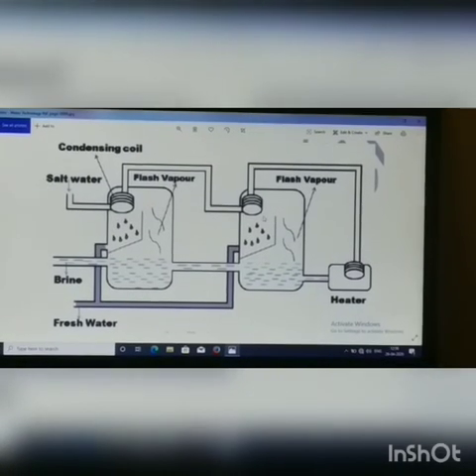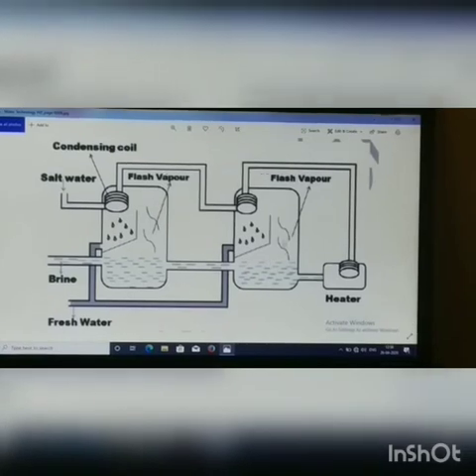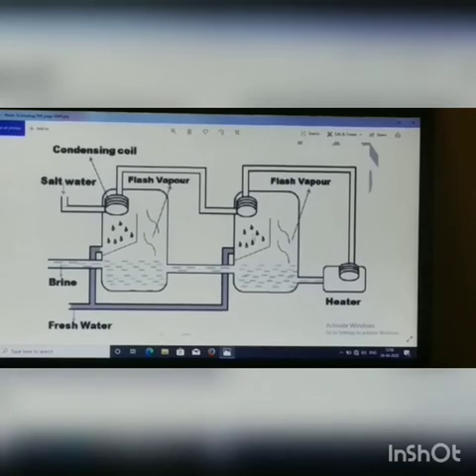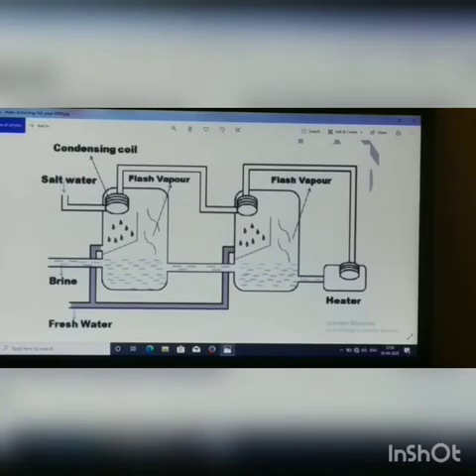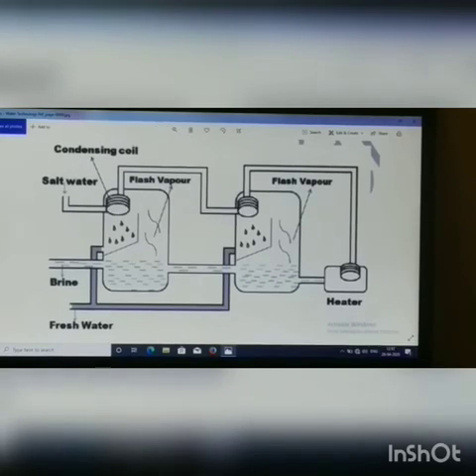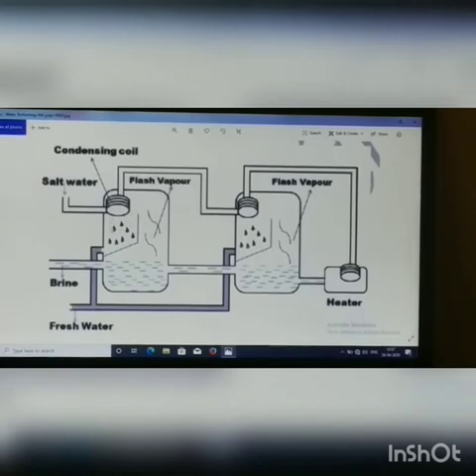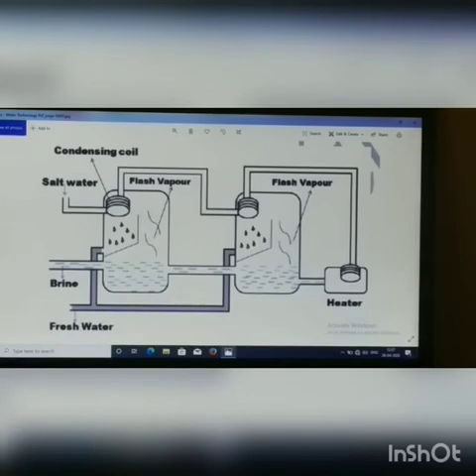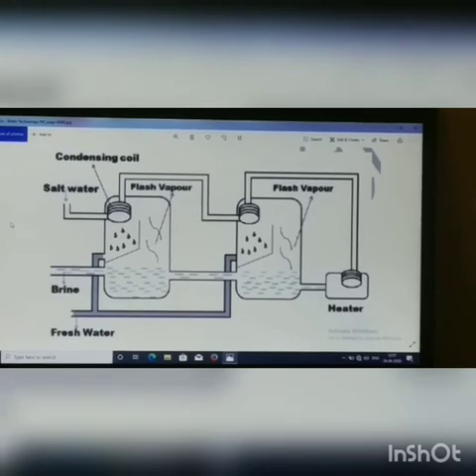At a lower pressure compared to atmospheric pressure, the water starts evaporating. These vapors are collected at the condensing unit and fresh water flows out. The brine further moves into the second flashing unit where the pressure is lower than in the first unit. At this lower pressure, water again starts to evaporate, the vapors are condensed at the condensing coil, and they are collected as fresh water.